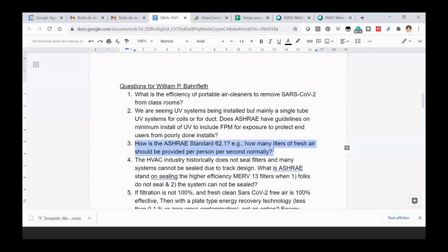So it basically goes back to, for example, Fanger's experiments on ventilation rate and satisfaction level, and of course that gets us to about 7 liters per second per person for 20% dissatisfaction, which works out to about 15 CFM per person in our obsolete U.S. unit system.